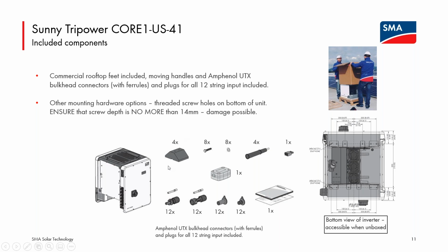And we have moving handles, commercial rooftop feet included with each unit. But if you're not going to use those commercial rooftop feet, each inverter ships on its side on its own little pallet. And when you take the box off of it, you have immediate access to the bottom of the inverter where those commercial rooftop feet would mount, or if you were maybe attaching the inverter to the actual racking structure, maybe it's a very high wind area and you need to lock down the inverter in a little more secure manner, you have immediate access to those threaded screw holes on the inverter body at the bottom immediately out of the box.